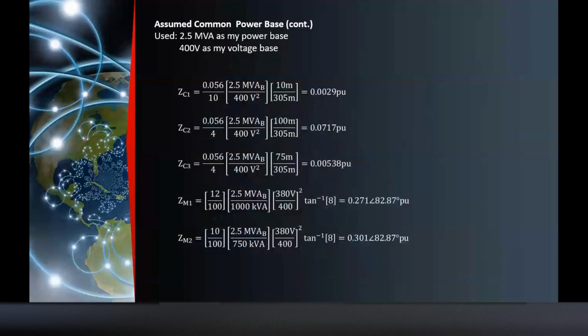So again, the ohmic value of the cable, we convert it into per unit: 0.056 divided by the number of sets, multiplied by your MVA base, divided by 400 V squared. Okay? Times 10 divided by 305 meters. Sir, why 305 meters? Because you want to know the impedance with respect to only 10 meters, since the 0.056 earlier is based on 305 meters. So automatically, if the length of your cable is 305 meters, that is 0.056.